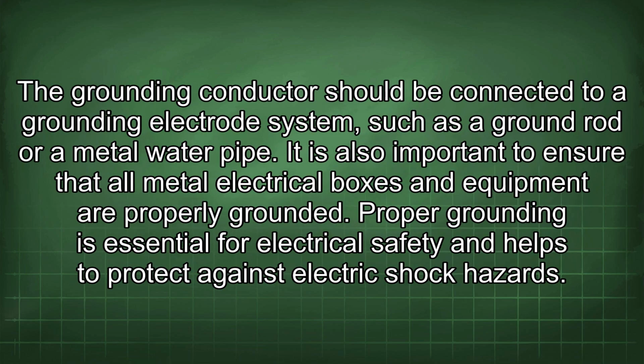The grounding conductor should be connected to a grounding electrode system, such as a ground rod or a metal water pipe. It is also important to ensure that all metal electrical boxes and equipment are properly grounded. Proper grounding is essential for electrical safety and helps to protect against electric shock hazards.